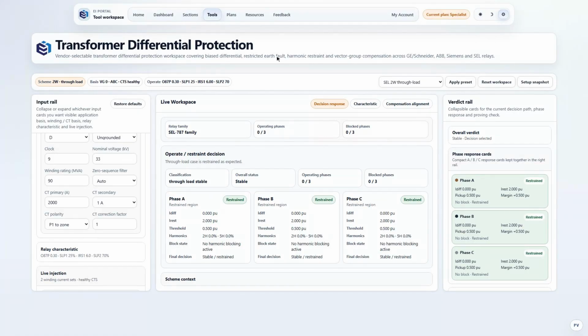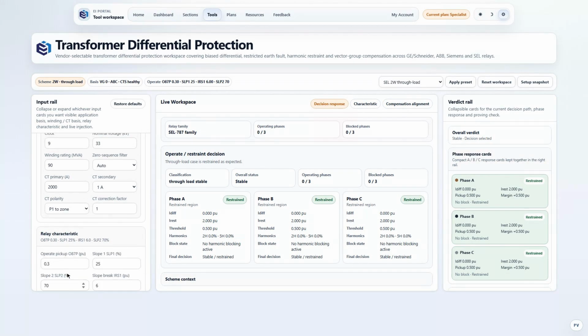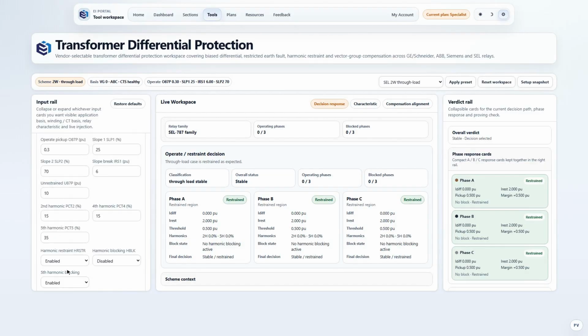The group settings load as the factory defaults from the 787 manual. Minimum pickup, O87P at 0.3. A first slope of 25% rising to 70 past the break at 6, an unrestrained pickup at 10, and second and fourth harmonic thresholds of 15%, with the fifth at 35 and harmonic restraint enabled. Nothing invented, nothing tuned to flatter the demo.